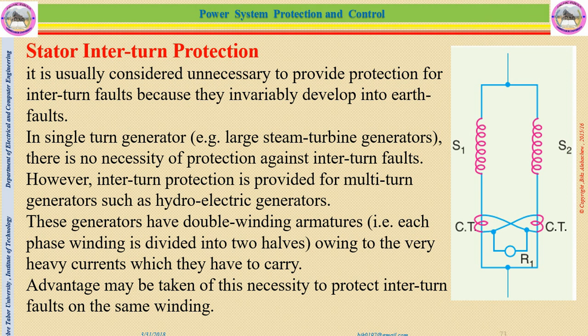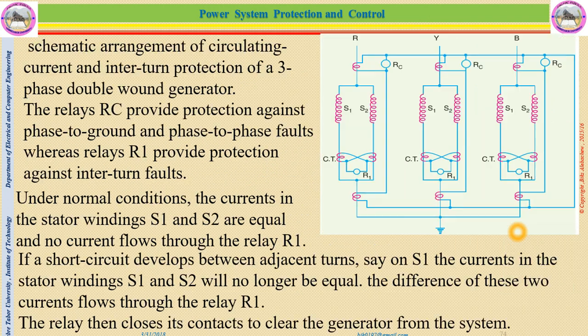Look at this one. This is the protection of a hydro generator. S1 and S2 may be found in parallel. So there is the inter-turn fault protection relay, R1, which is required. So the two currents will be compared in the S1 and S2 windings. If a fault happens on S1 or S2, there are no longer equal currents in the two windings S1 and S2. This is the schematic arrangement of the circulating current and interturn protection of a three-phase double winding generator. This is a general protection.